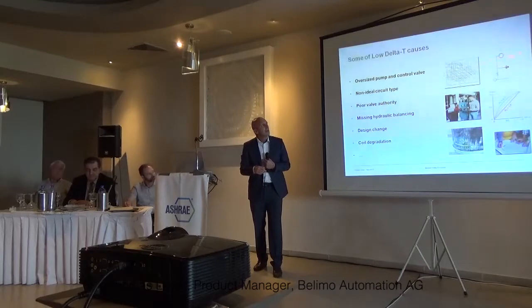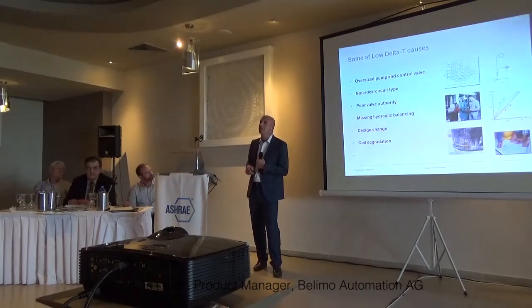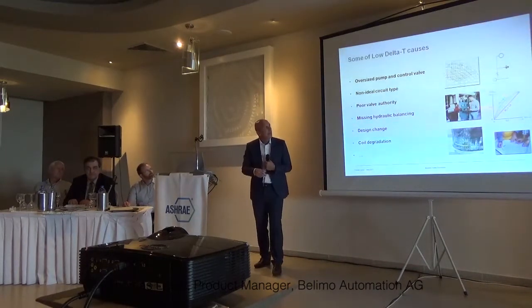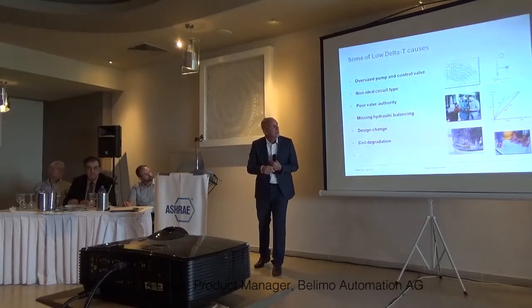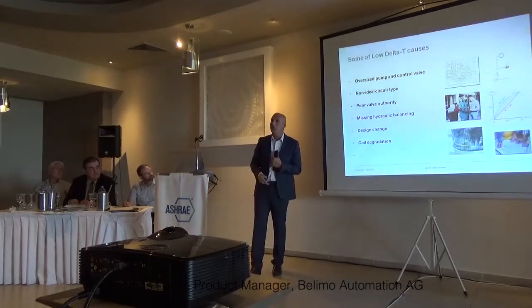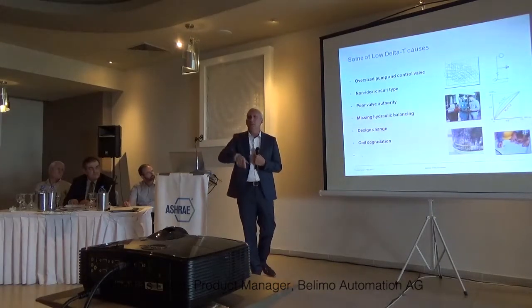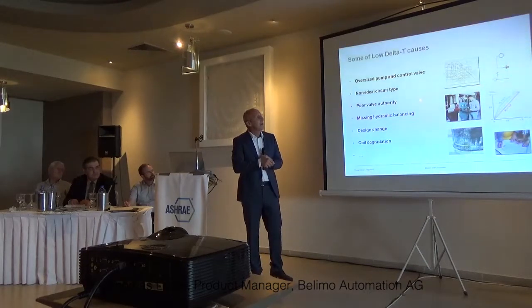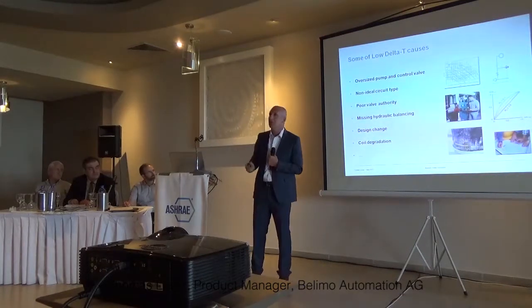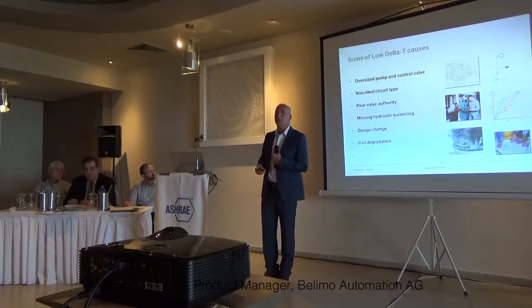Once you close, or once you lock out this device at the end, all the water will flow more or less unused with one temperature level right back to the return. It comes here with 6 degrees, enters here, and goes back with 6 degrees. Delta T stays extremely low.